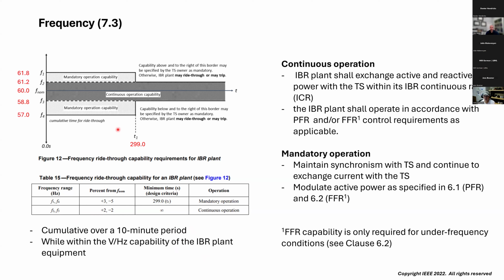When you're in a mandatory operating mode or the continuous mode, what the IBR needs to do is really reference back to clause 6, which is the primary frequency response and fast frequency response requirements. And note that fast frequency response right now is only applicable for under frequency conditions, but all of the frequency response performance is specified in clause 6.